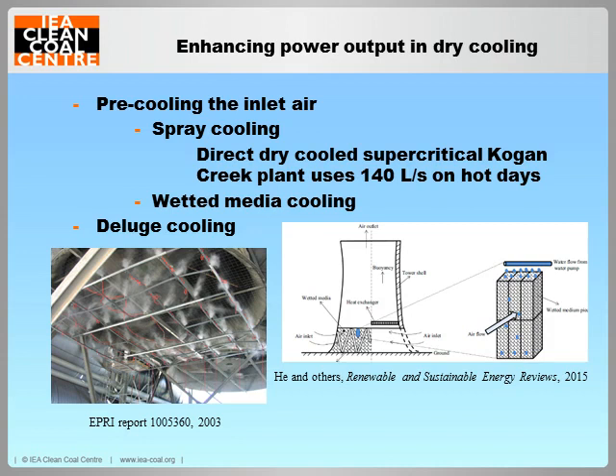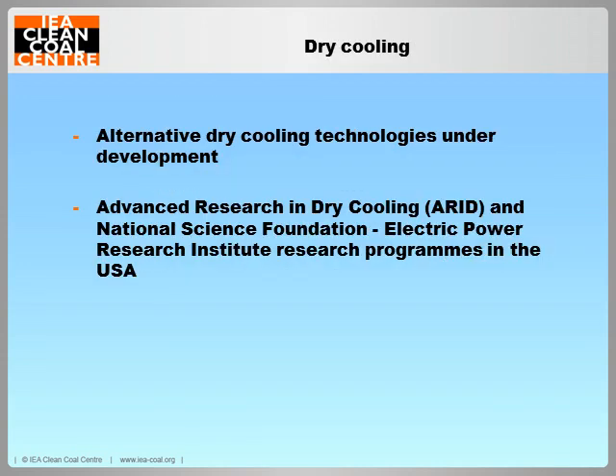In a deluge cooling system, water is introduced onto the outside of the heat exchanger tubes. And here it runs down the fins as a thin film, and the excess water is collected and recirculated. It requires more water than the spray and wet media cooling systems. A lot of research is being done to diminish the disadvantages of dry cooling and to develop alternative dry cooling technologies. The USA, for example, has 2 research and development programs that are specifically targeting dry cooling, and these are listed on this slide.